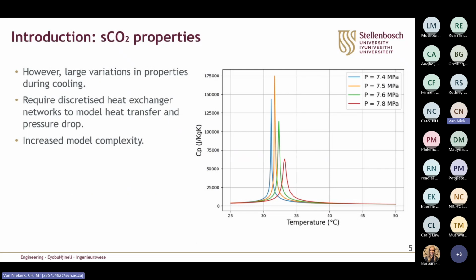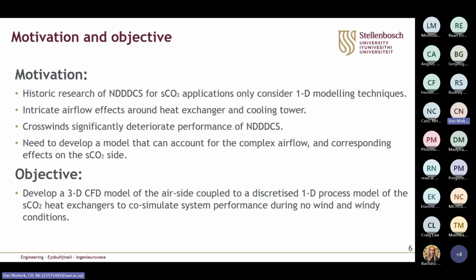However, there is a unique challenge when it comes to the modeling and designing of these SCO2 cooling systems, as during cooling, the thermodynamic properties of SCO2 significantly vary, which makes the use of typical lumped parameter modeling approaches quite inaccurate. For example, when looking at the specific heat of SCO2 across 4 different pressures, the SCO2 cools down and reaches near the critical point where the specific heat can vary by 1 to 2 orders of magnitude. This makes the prediction of the heat transfer and pressure drop quite difficult to do with lumped parameter models, and therefore we need discretized heat exchangers to accurately account for those property variations.